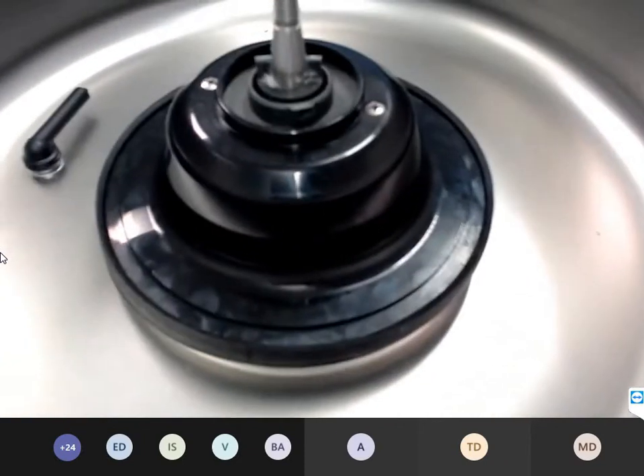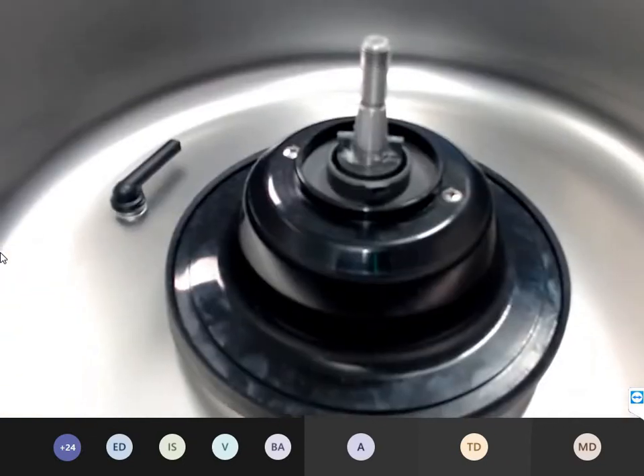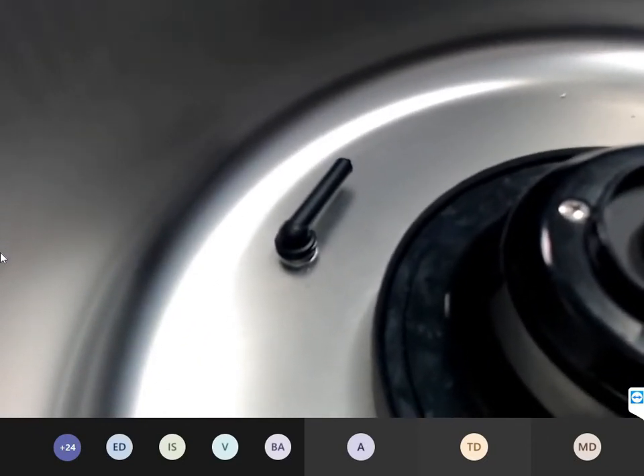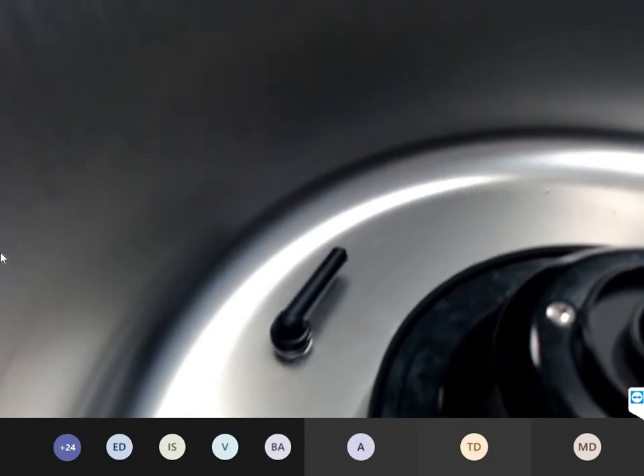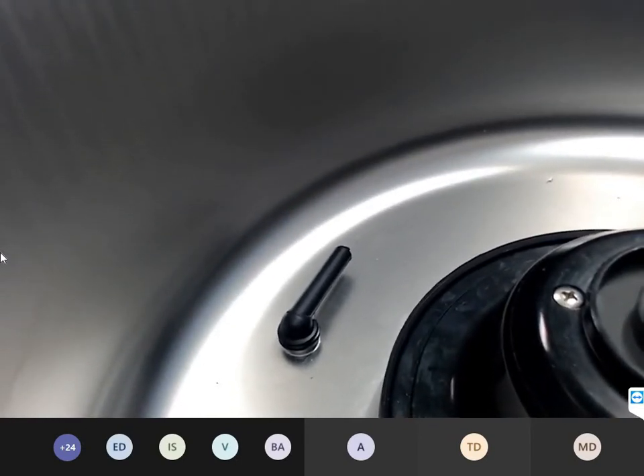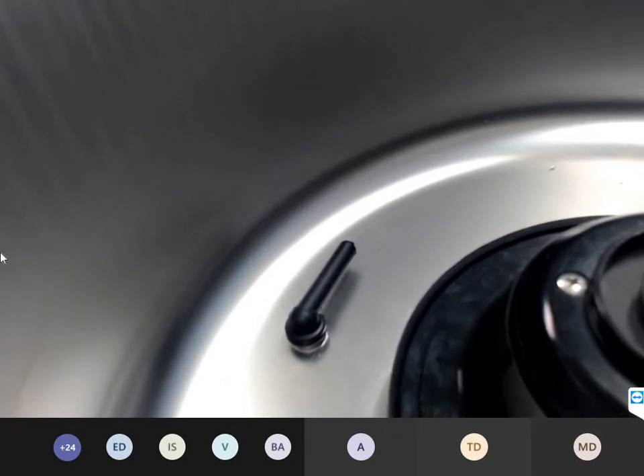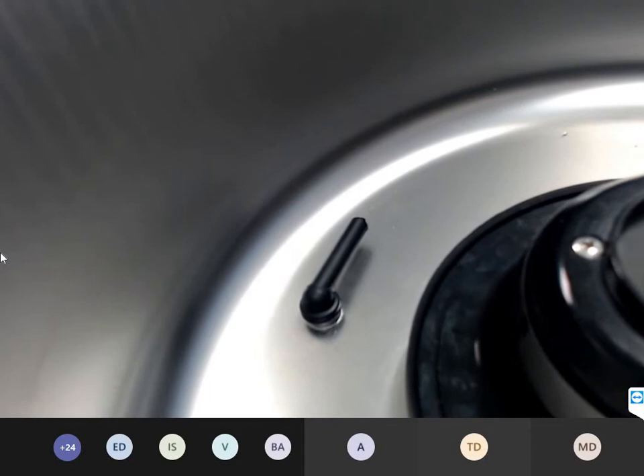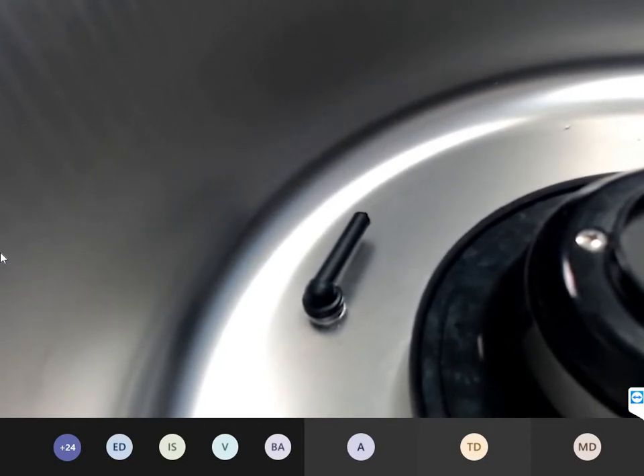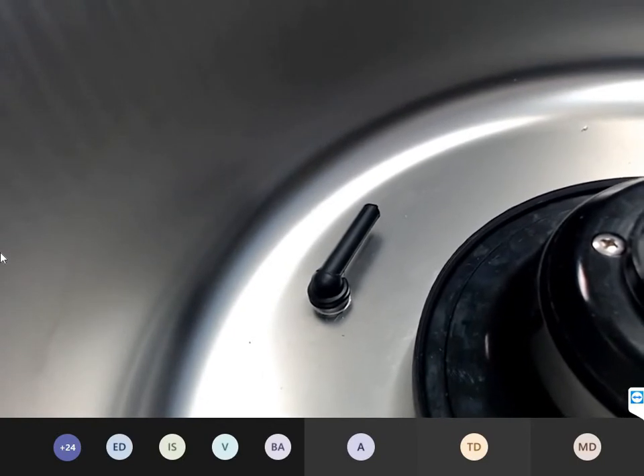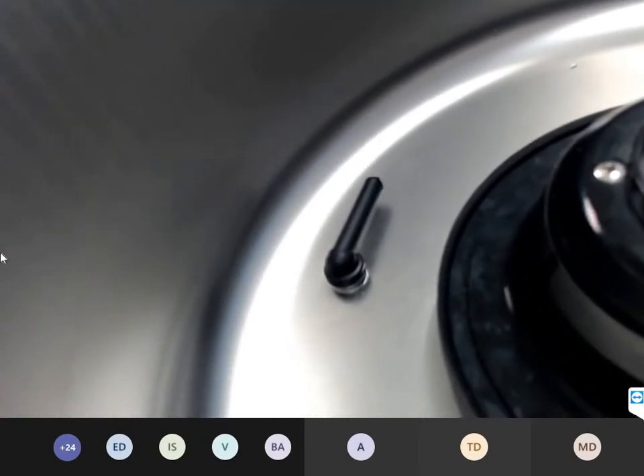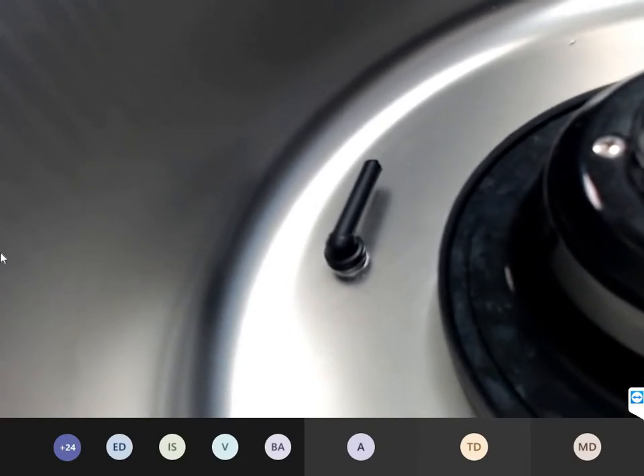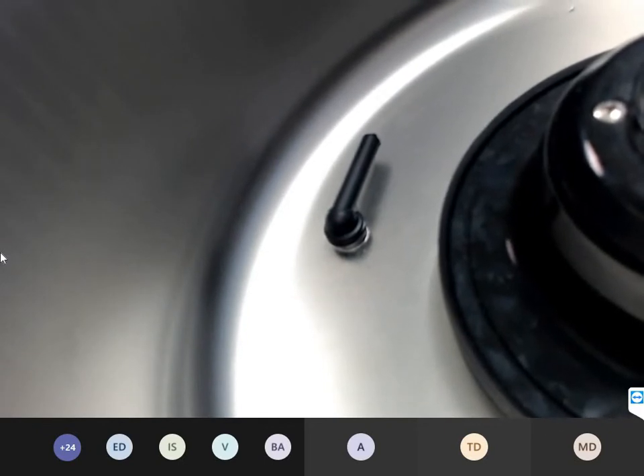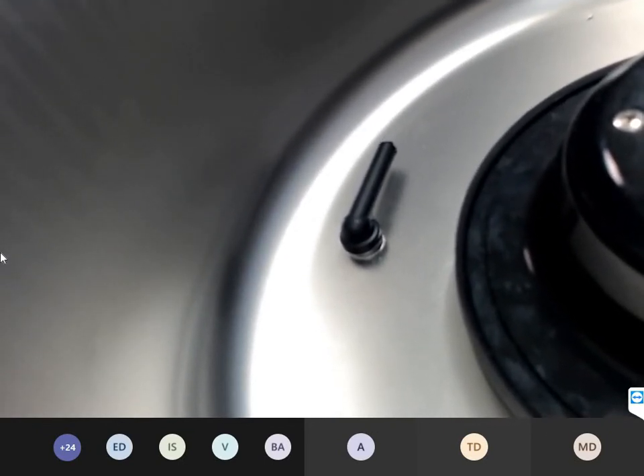That's it. And here, of course, the motor cover with the sealing ring. And this sensor here is also a temperature sensor, very important. In case of an error message with error code 93, in most cases this sensor is the issue. That means we have an interruption in the communication between the electronics and one of the slaves, like this sensor or the imbalance sensor, but in most cases this one is the reason.